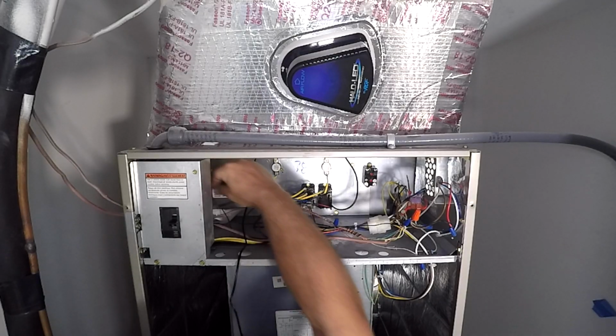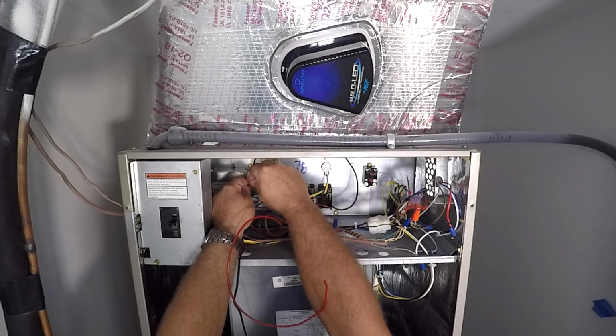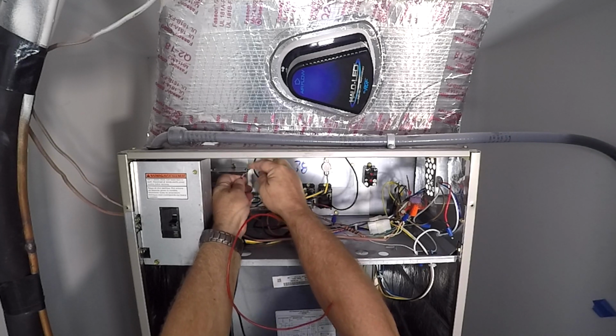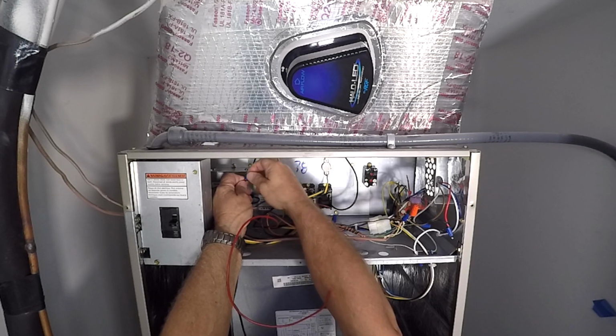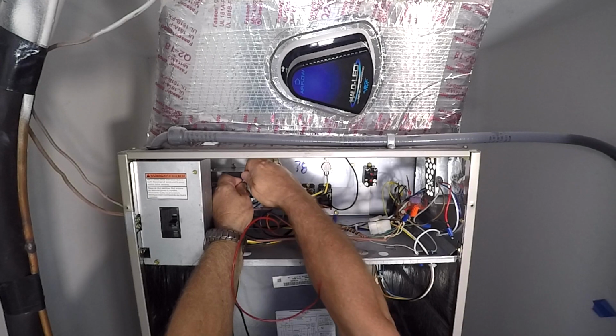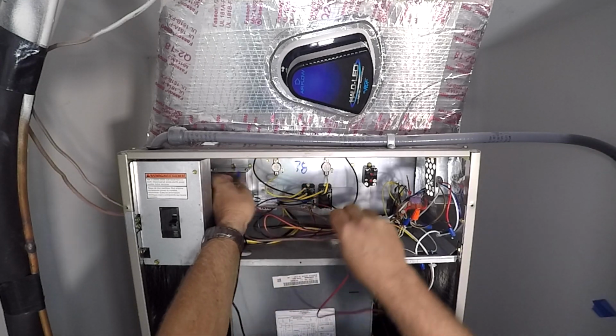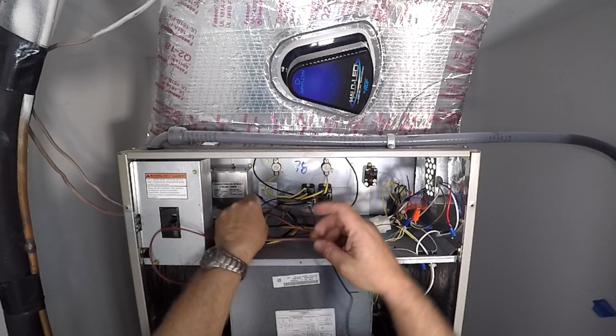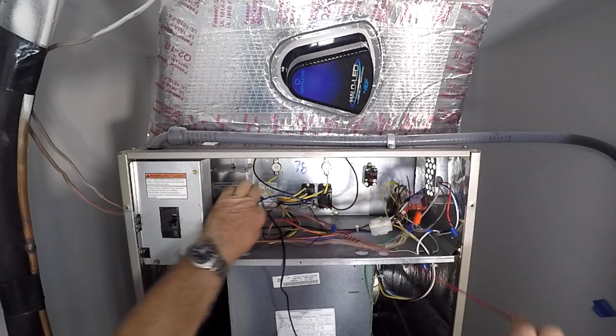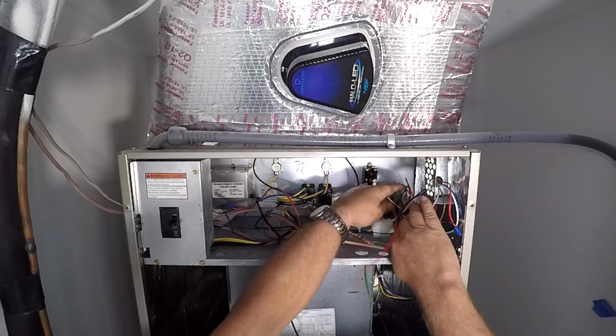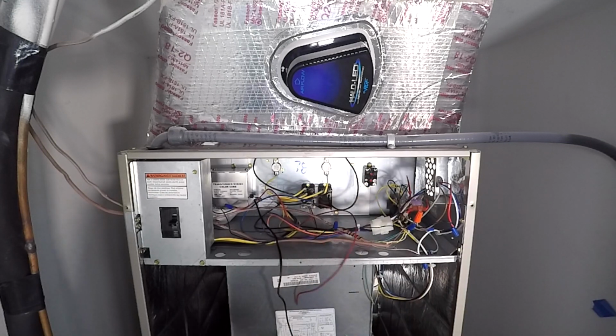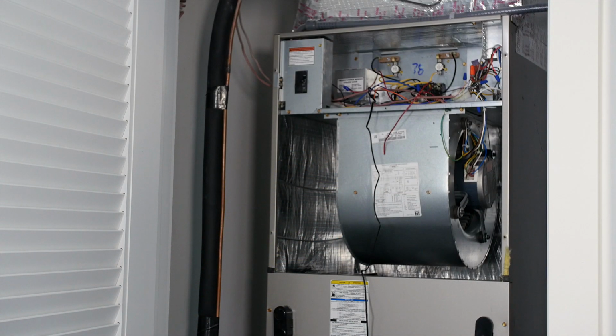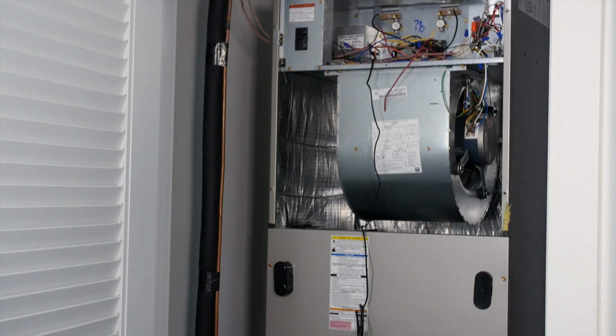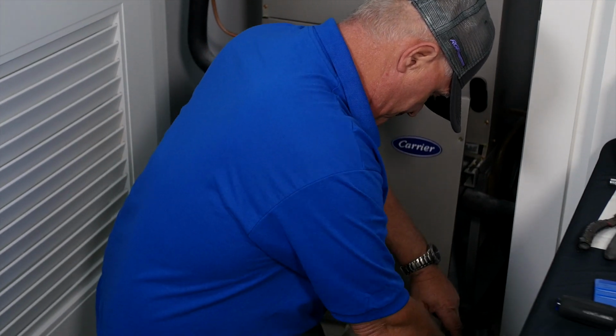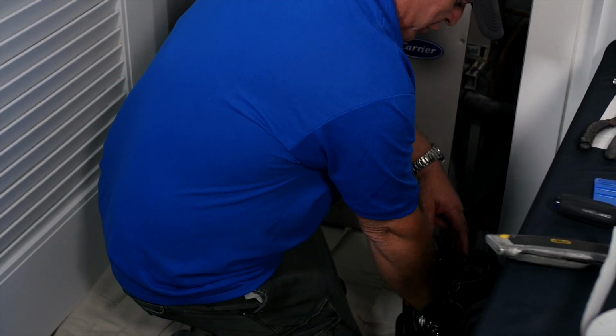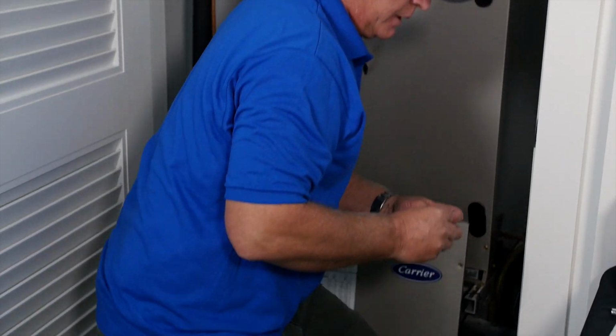As I'm doing the common high voltage wire first, which is the black on this particular transformer, I am going to connect the black to my line incoming black, and where I'm going to connect this is off of the existing low voltage transformer in the unit here. I'm going to do this by use of a line tap. Alternatively, you could cut the wiring and use a wire nut. I just prefer not to cut the wiring of the unit if at all possible.